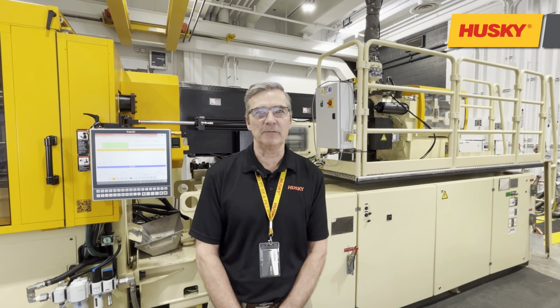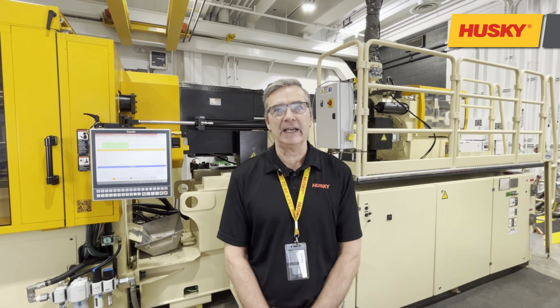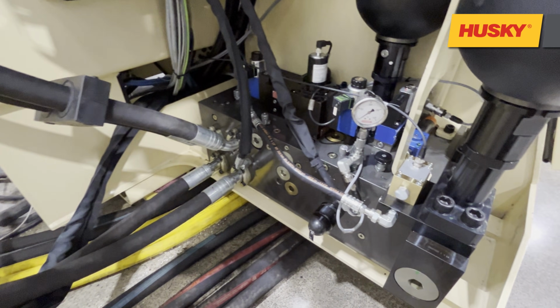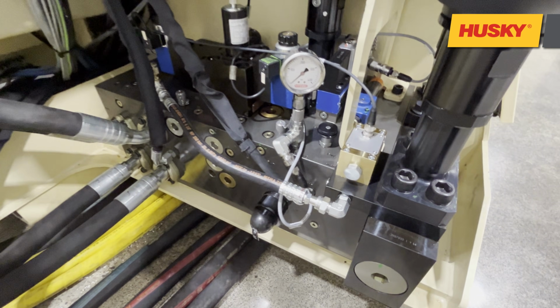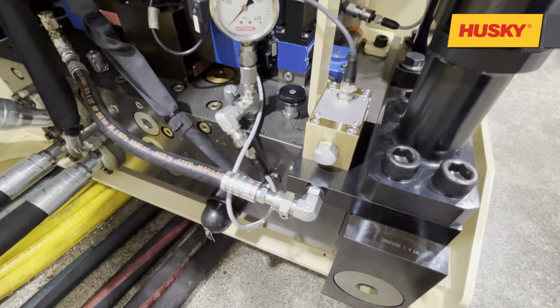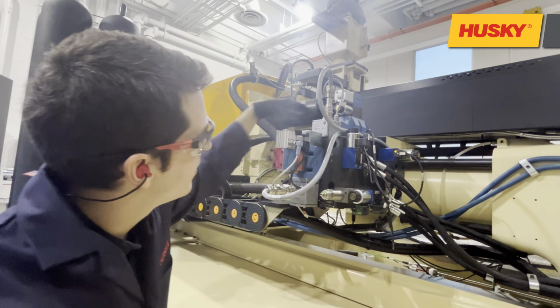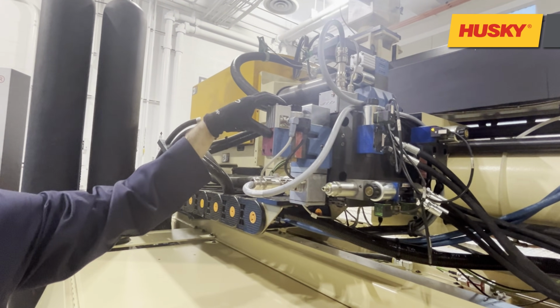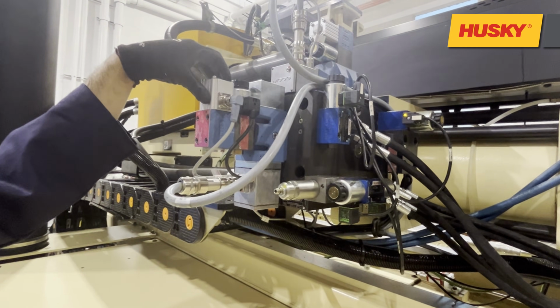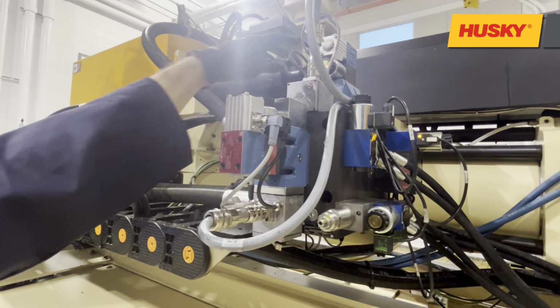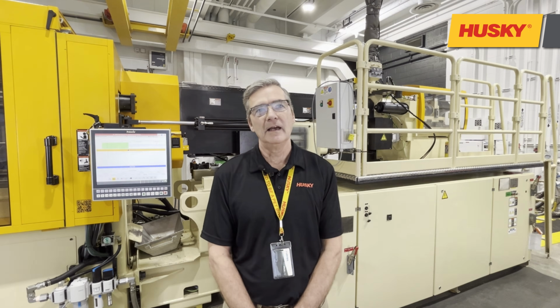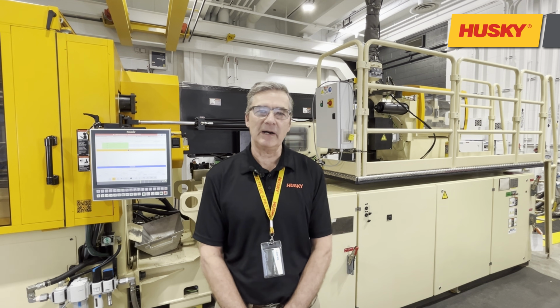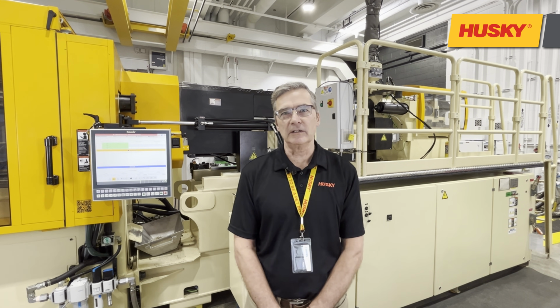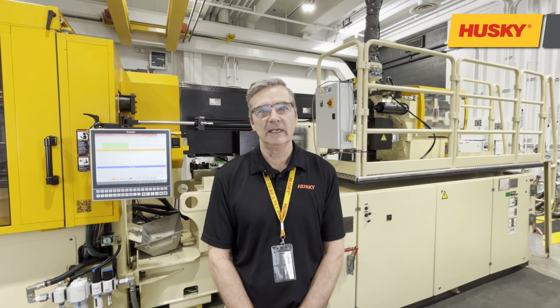Lately, we've been looking at ways of applying monitoring devices to provide actionable predictive maintenance information. Particulate and moisture contamination cause serious system failures if left unresolved. That's why we've developed the particle counter monitoring upgrade. This system reports cleanliness levels that directly affect servo valves and cylinders. By mounting the inline particle counter on the power manifold, we provide the earliest possible reporting of contamination, giving customers the earliest opportunity to act.